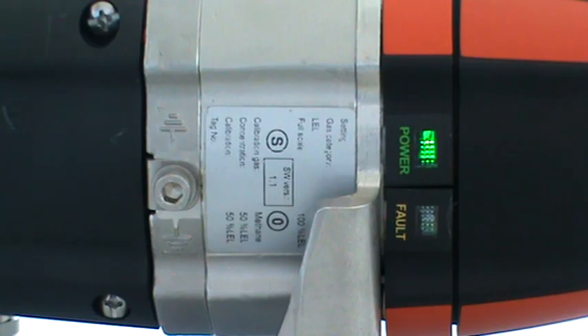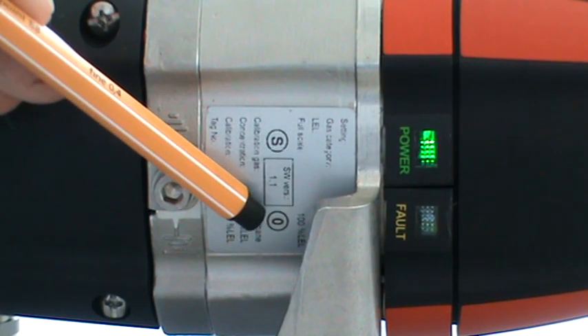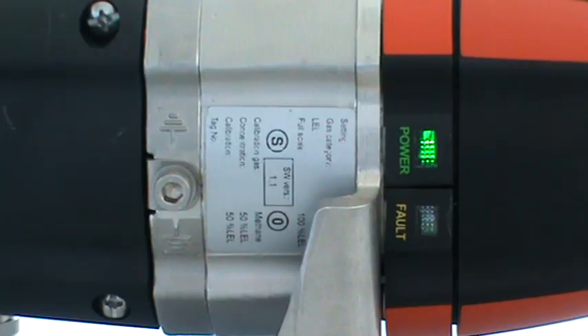Now, to start the 0-point calibration, meaning to enter the calibration routine, you hit, using the magnetic wand, twice on the 0 sign of the configuration label, which is here. This means you clearly bring the PIR 7000 into its calibration mode, in other words, into maintenance mode. Then, no longer a measuring signal, but the maintenance signal is transmitted from the gas detector to the control system. And you need to hit twice, because by following this pattern, your wish to enter the calibration routine can be differentiated from potentially present electromagnetic fields on site.